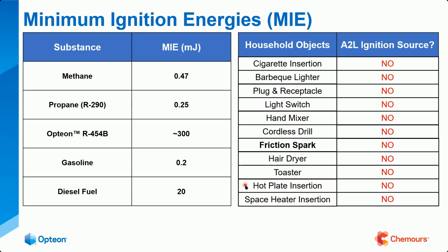In all seriousness, if you've got a ducted system, remember the mitigation strategies—you have that sensor that kicks on the fan, or G for you technicians, to lessen the concentration in and around the evaporator, since that has the potential of blowing into the house. For comfort cooling, residential and commercial, UL requires the sensor to go off at no greater than 25% of LFL, and until it hits LFL it's not even flammable. So these sensors are set way lower than the LFL.